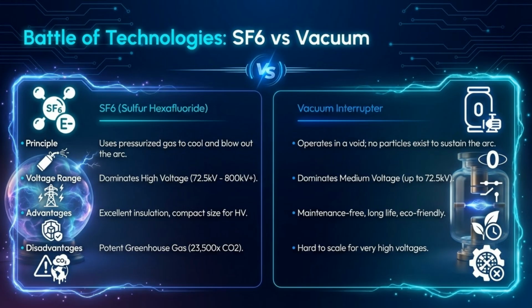We see a battle of technologies, SF6 versus vacuum. Sulfur hexafluoride, or SF6, dominates high voltage, using pressurized gas to cool the arc, but is a potent greenhouse gas. Vacuum interrupters dominate medium voltage and are eco-friendly, but are hard to scale for very high voltages.